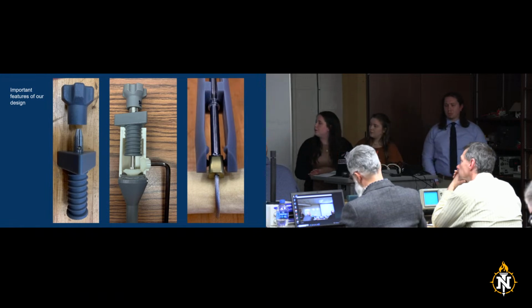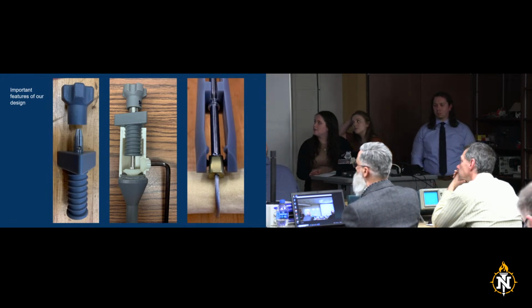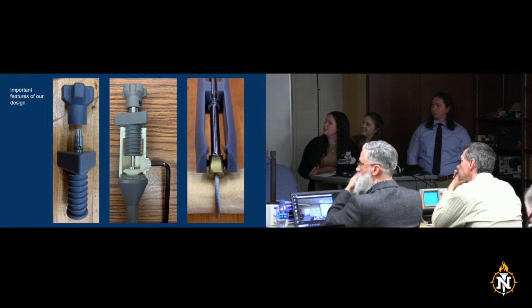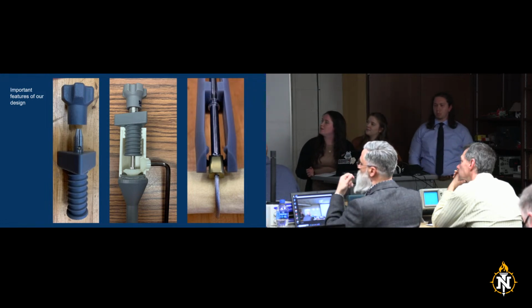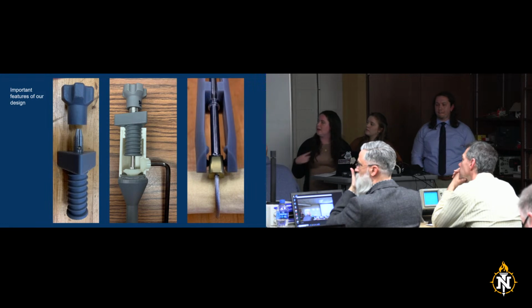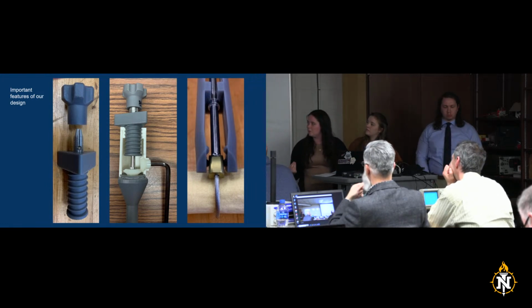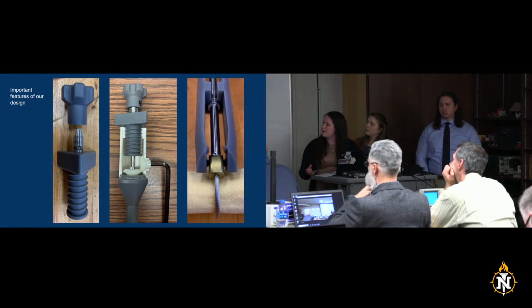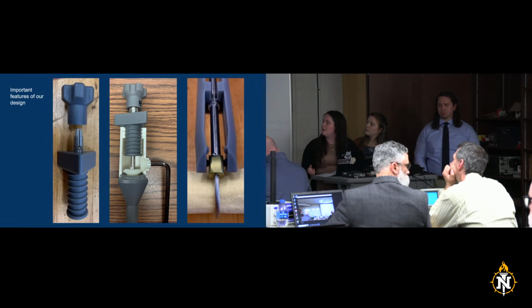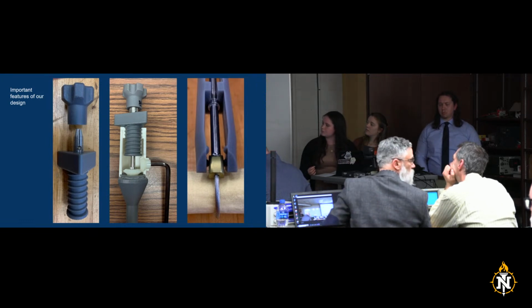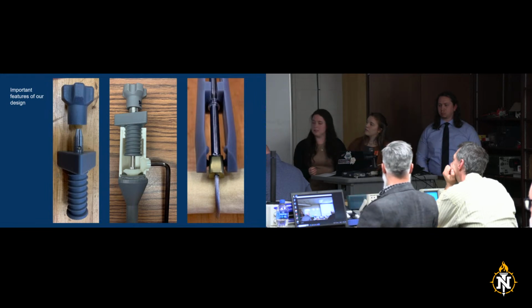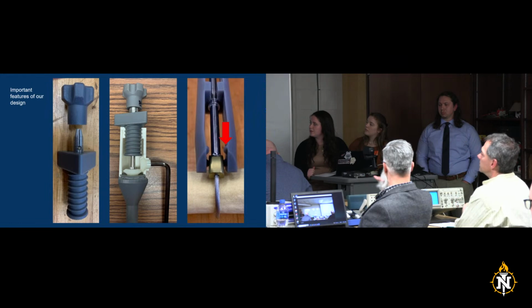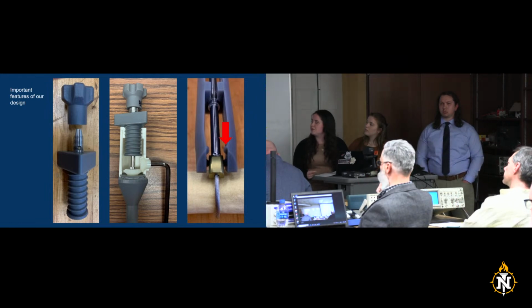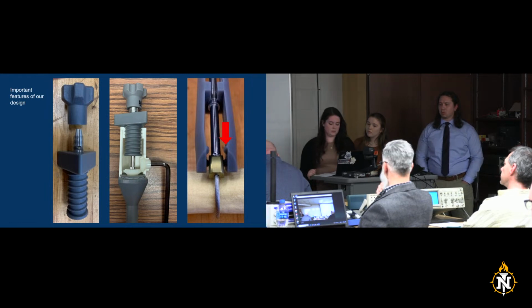There are three important interfaces of our design. On the left side, or on the far side, you can see a collet with a star knob. The star knob tightens down and tightening the collet onto the cable. In the middle, you can see the inside of the assembly where the gears and the tensioner are located. And on the far side, you can see where the implant attaches to the device. It attaches with two dimples on either side of the implant and two teeth that attach to the implant.